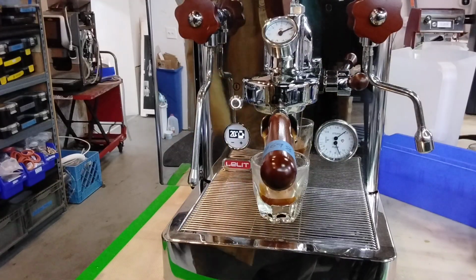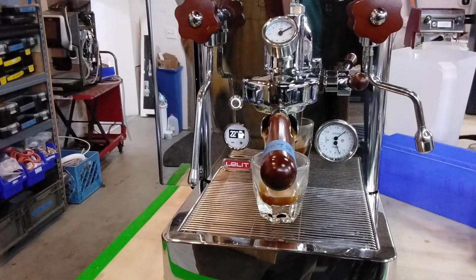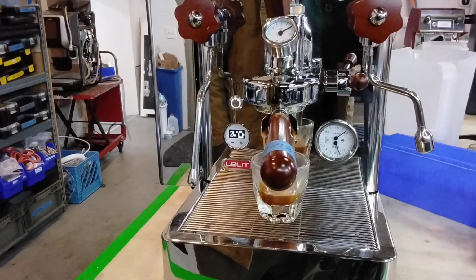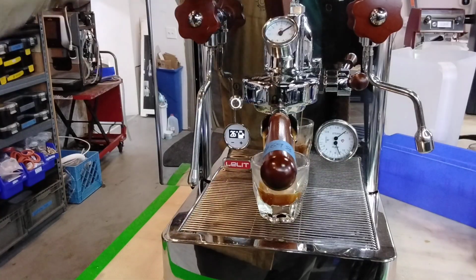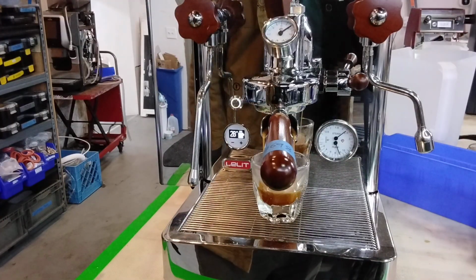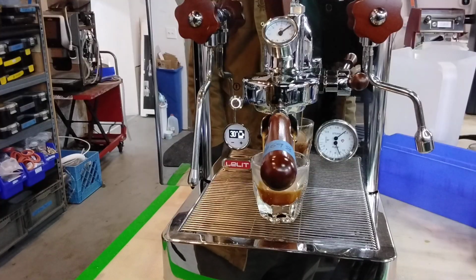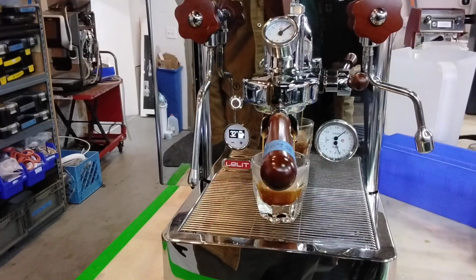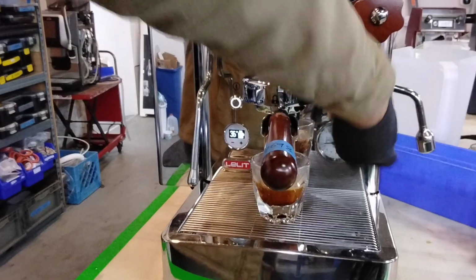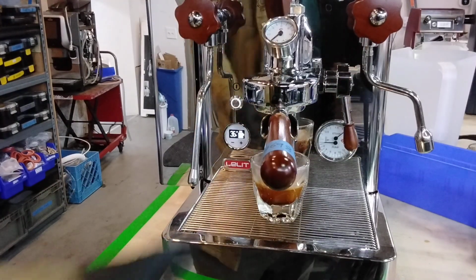The machine soon needs to replace the group head gasket, and it needs deep cleaning there. I tried to clean it as much as I can, back flushing it and cleaning around that gasket, but the customer decided to do it himself.